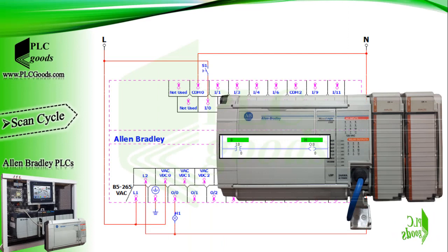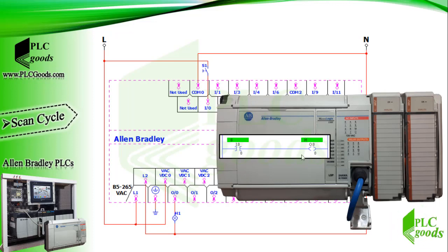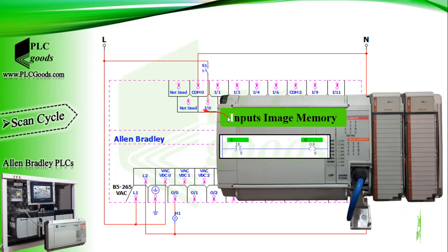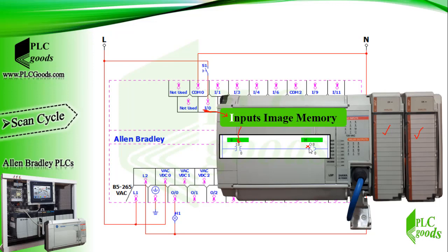In the previous video I used my Micrologix 1500 and its connected switch to turn on a lamp. Now let me explain how a PLC executes its program. When a PLC is in run mode, it stores the state of digital inputs and all other connected inputs such as analog inputs in what is called the input image memory. The PLC processor then continually solves the user logic program based on the current input image memory.